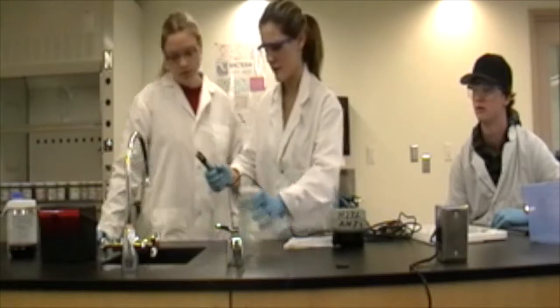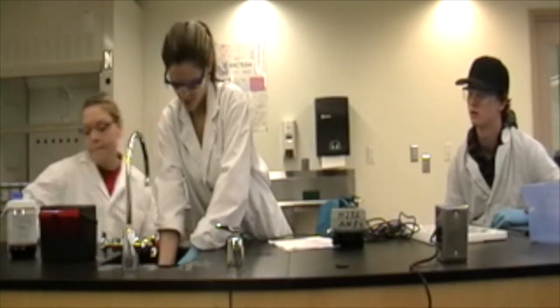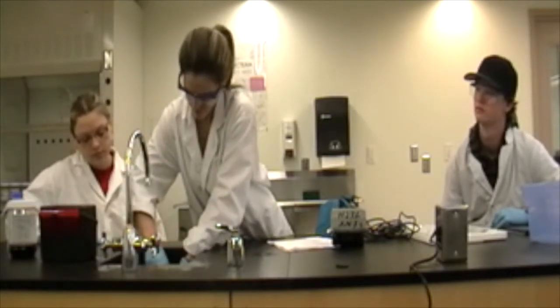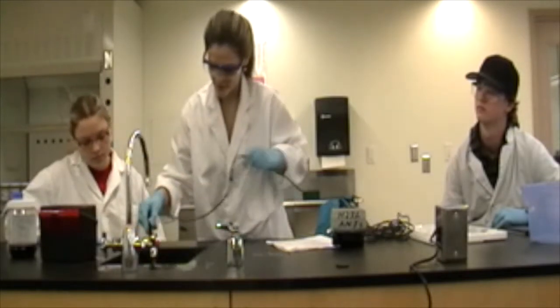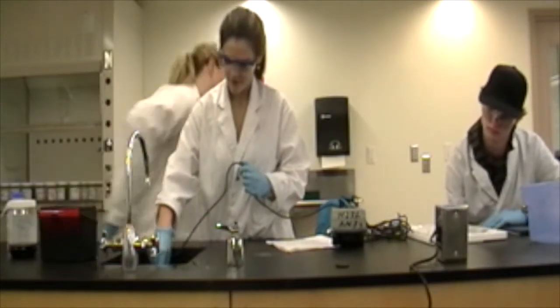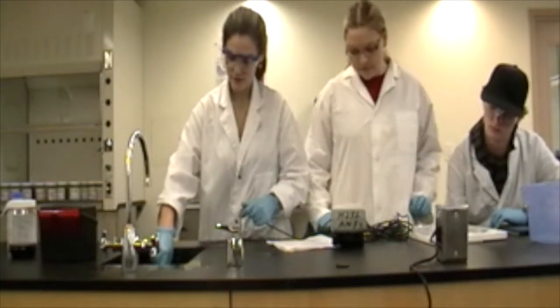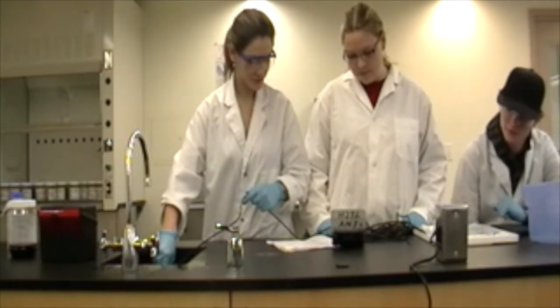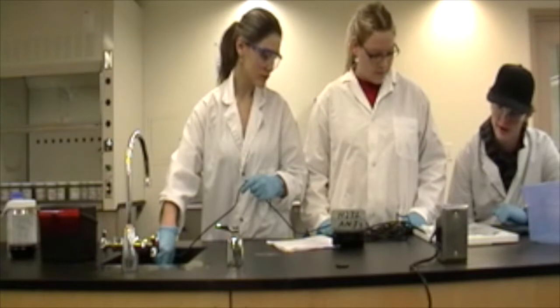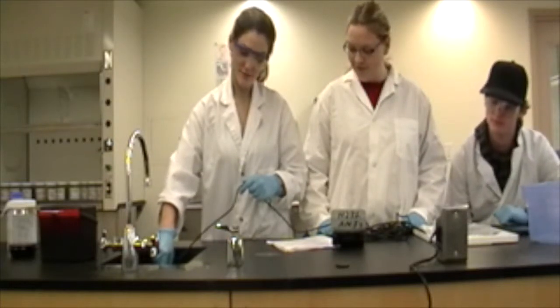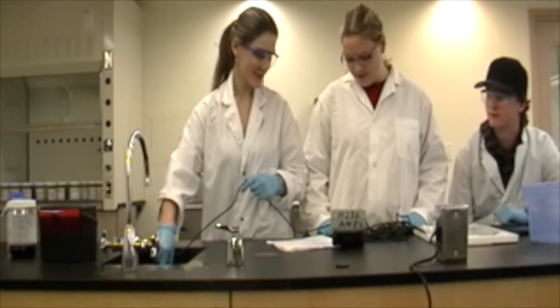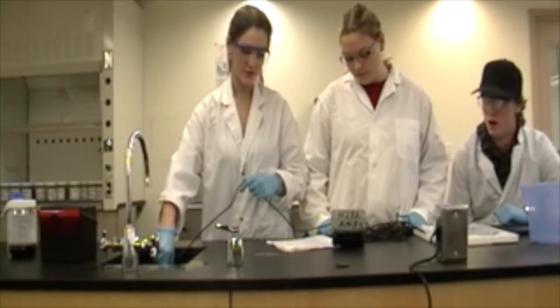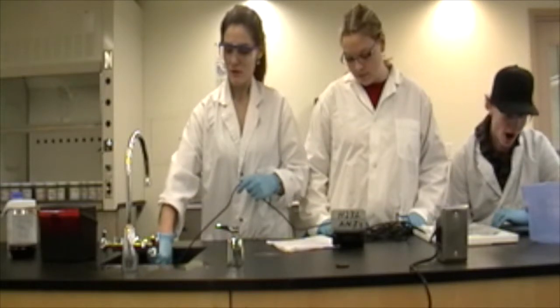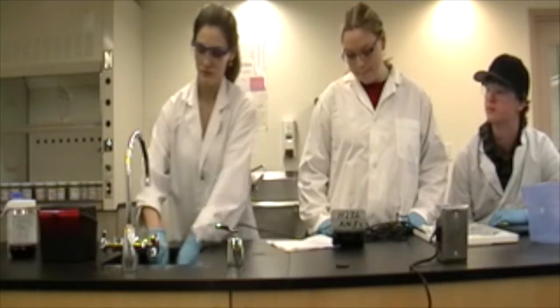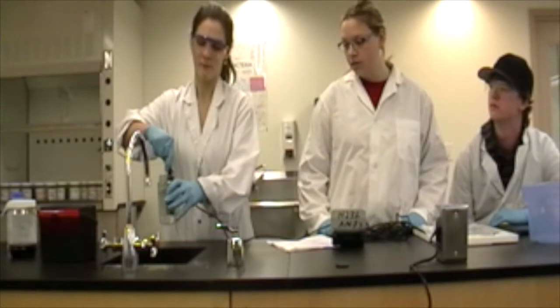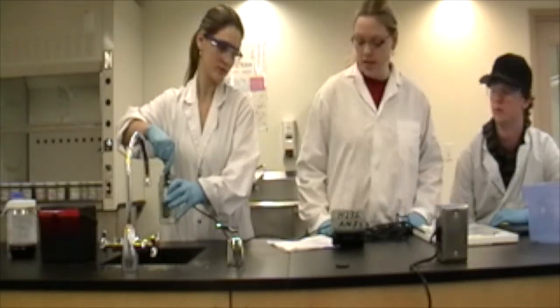Alright, so now we're going to open up our sample. Just going to do it in the sink. Alright, put the DO probe in. And we're going to be continuously mixing it to get a proper reading. You want to keep stirring the probe at a half foot per second. It's pretty fast. I got this. So you're going to want to do this until your reading stabilizes. Well, the temperature is 21.3 degrees Celsius. It hasn't changed.